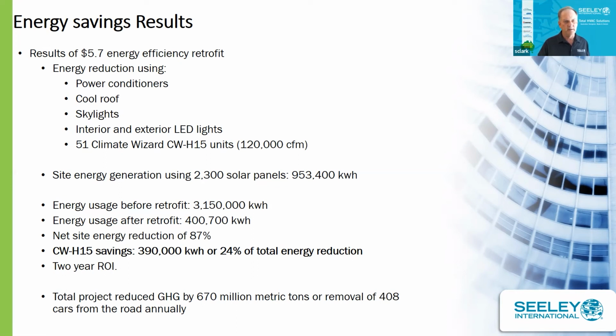CWH15 units. The site, in addition to that, had about 2,300 solar panels that generated about 1 million kWh. The energy usage before the retrofit was about 3.15 million kWh. Energy usage afterwards was 400,000 kWh. This is an 87% net site energy reduction. And our units contributed about 24% of the energy savings for all these methods. It saved about 670 million metric tons of CO2, or the removal of about 400 cars.